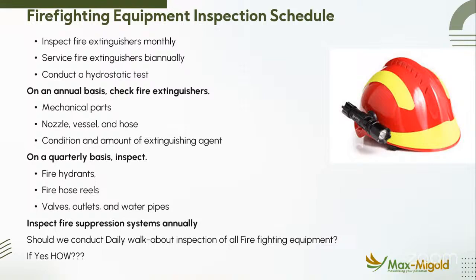So some of us even do what we call a daily walk tour or walkabout, meaning that we are not going to carry out a deep inspection of fire extinguishers, but we check. What do we check? The condition of the hose or horn and the gauge of the DCP. If the gauge is flat, it shows that it has been used. If the pin is missing, it shows that something went wrong. If the hose is in bad condition or loose or missing, it shows that when there is fire, you cannot even use that extinguisher. So on a daily basis, when you walk past an extinguisher, please don't just look away.